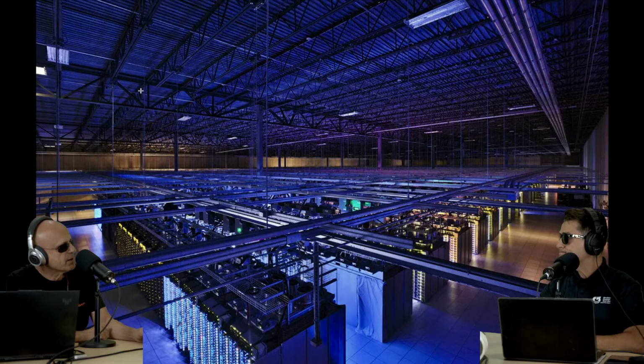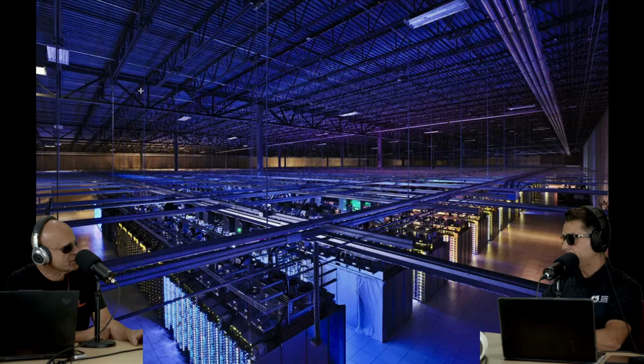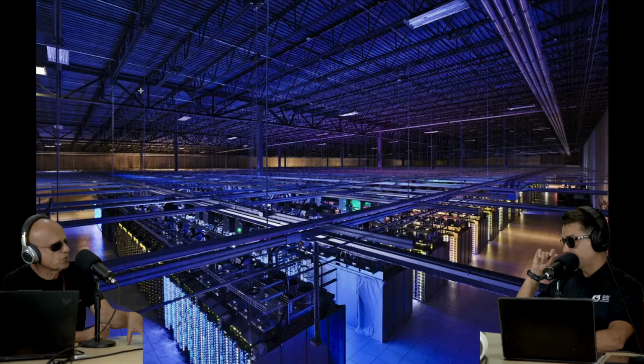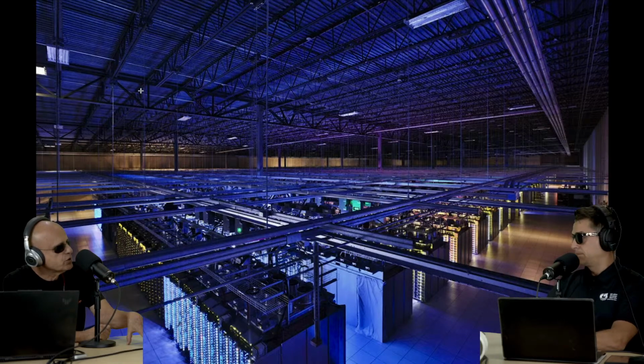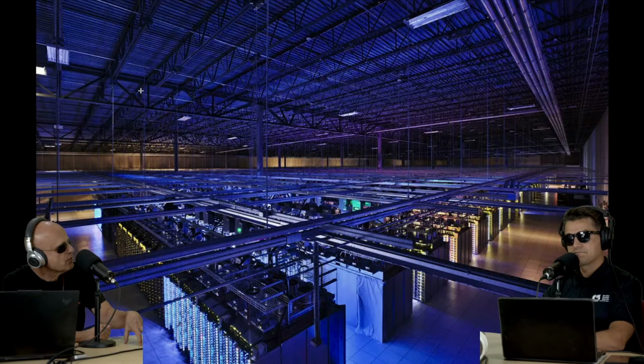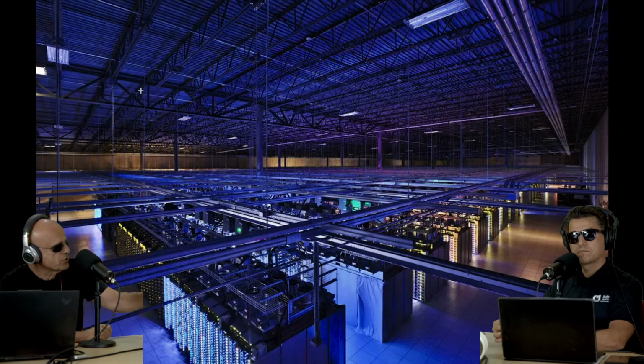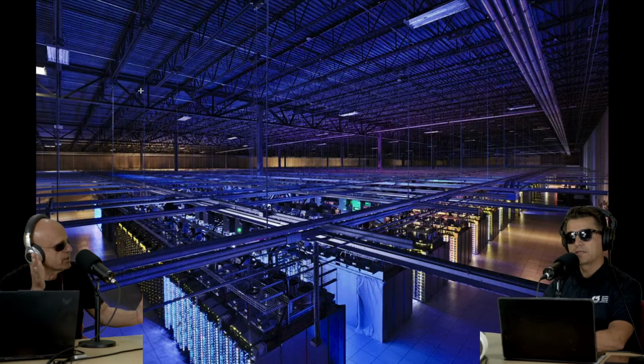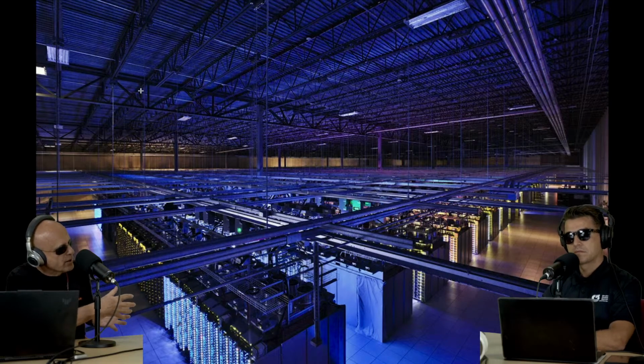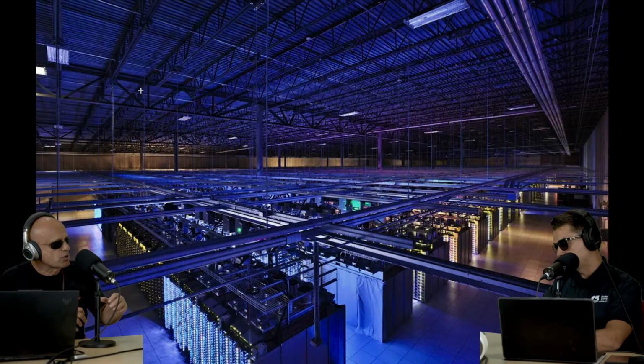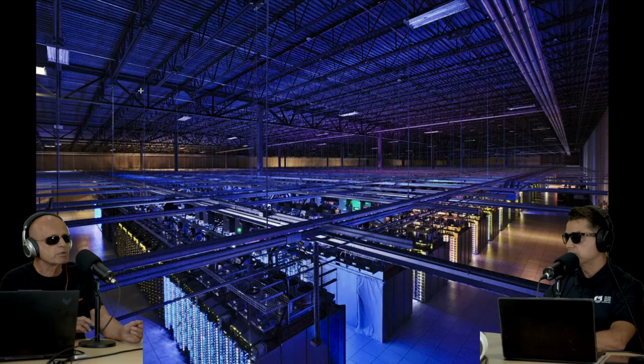That's another advantage of having an access floor system. In an access floor construction, you can use the plenum or cavity underneath for providing cool air or moving air around. You do that with vented floor tiles, usually 24 by 24 inch, placed in front of the equipment where it draws air from. So as you move equipment around, you move the vent tiles with it to take your cooling along.